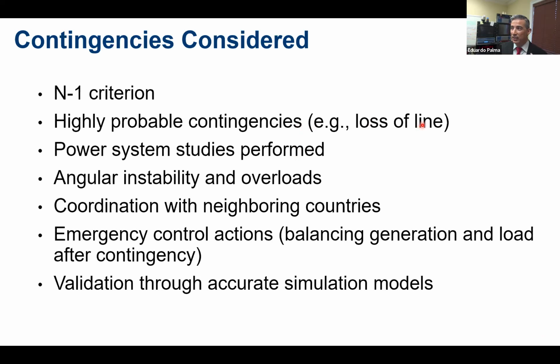One of the examples is just the loss of the line, which does happen, and not only because of accidents, but because of weather. It is very important for GSE to be ready for the cold season, when the weather gets extremely cold and there's ice on the transmission lines, right? So power system studies were performed, and when you do perform them through experts, you arrive at lots of hypotheses that need to be validated.